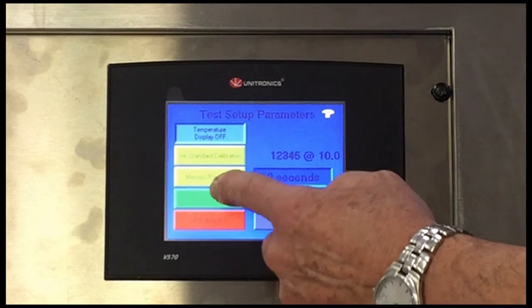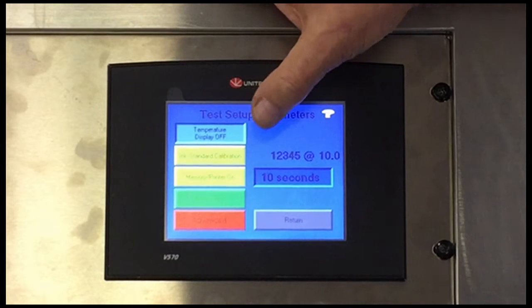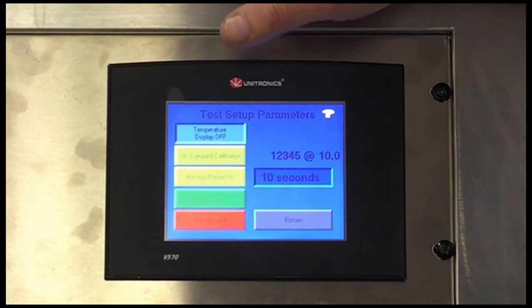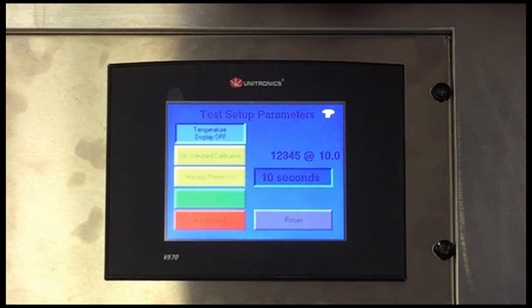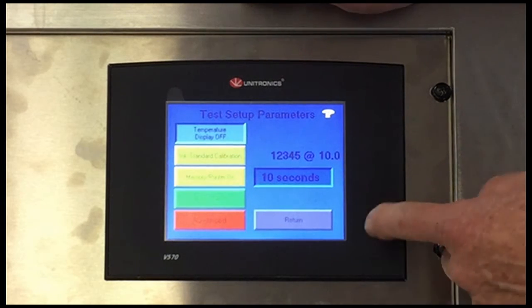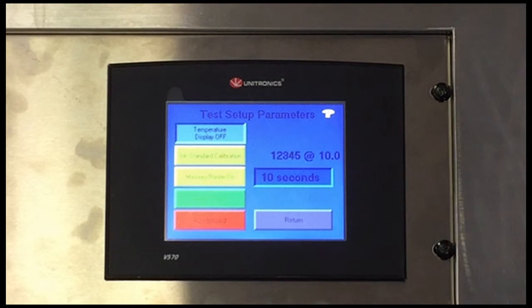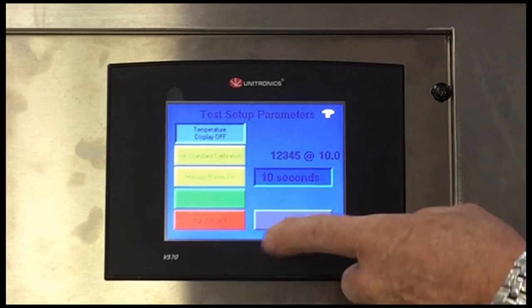Now the memory and the printer on. If you recall, when we ran the automatic test a little while ago, every 10 seconds you would hear a beeping sound coming out of here, and we would get another line of data over here, and it would latch the tack number on the display until the next timeout. Well, this is where we're actually setting the timeout.